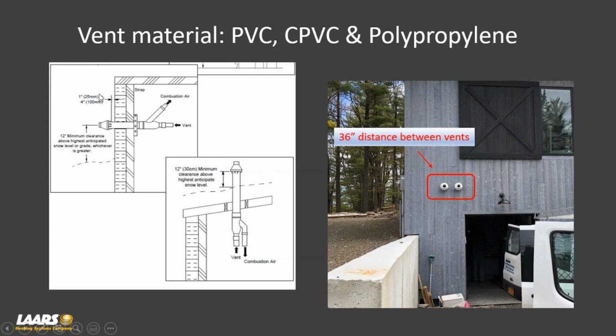And what we're showing here is the concentric kit. This is more of the bazooka style, which is fine. We're certified for that. We're also certified for the flush mount kit. But also read the manufacturer's instructions. Example of that: how many times have you gone into or driven past a home and you'll see these sticking off the dwelling 8, 10, 14 inches out? That instruction sheet tells you 1 inch off the dwelling, because having your vent cap out here, so there's your exhaust, here's your combustion air, having it out here, you can get flue gas recirculation, especially in low fire. You're not forcing those flue gases 3 feet away from the vent. They're trickling out right here, a little wind, and they get drawn right back in. Multiple units should have a distance of 36 inches, 3 feet apart, so you do not get flue gas recirculation.